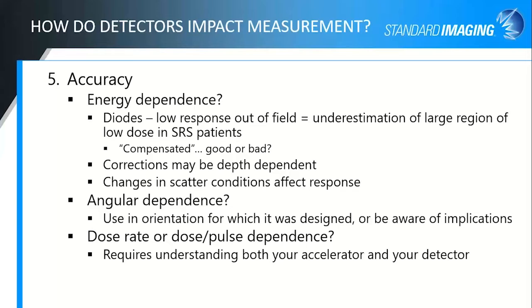Angular dependence of your detector is a little bit less critical when you're doing just face-on scanning in a water tank, but it is important to make sure that you're using your detector in the orientation for which it was designed. If you turn your ionization chamber end on, or if you turn your diode on its side, make sure that that's actually been characterized before you expect to be able to use it.